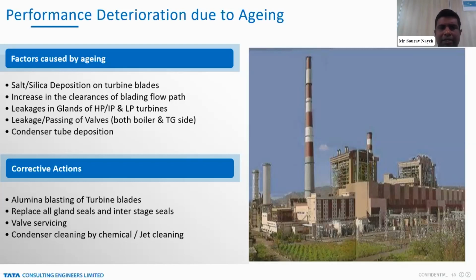Now, what are the corrective actions? For turbine blades, we should do alumina blasting. With alumina blasting, we will definitely maintain the turbine blade smoothness. We can avoid the roughness of the blade and we can improve the efficiency of the turbine. The gland leaks and interstage seal leaks also should be repaired. We should maintain the seal strip leakages to a minimum level, and the condenser also should be cleaned by different cleaning methodologies, so that our overall performance is maintained.